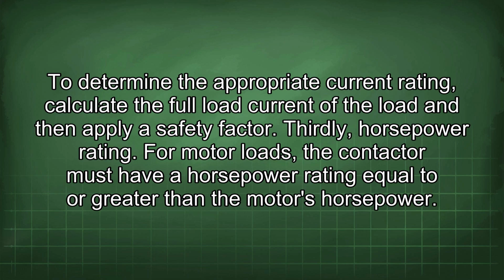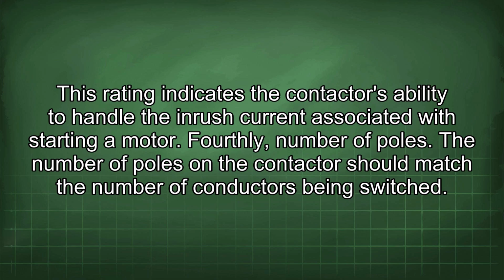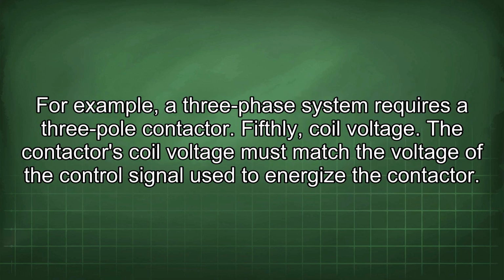To determine the appropriate current rating, calculate the full load current of the load and then apply a safety factor. Thirdly, horsepower rating. For motor loads, the contactor must have a horsepower rating equal to or greater than the motor's horsepower. This rating indicates the contactor's ability to handle the inrush current associated with starting a motor. Fourthly, number of poles. The number of poles on the contactor should match the number of conductors being switched. For example, a three-phase system requires a three-pole contactor.